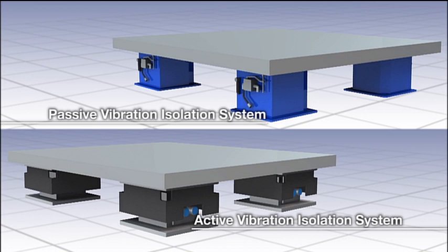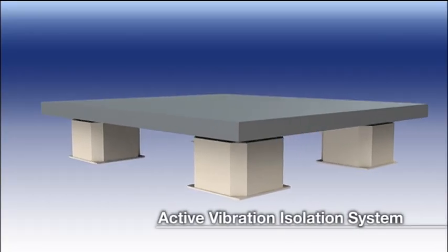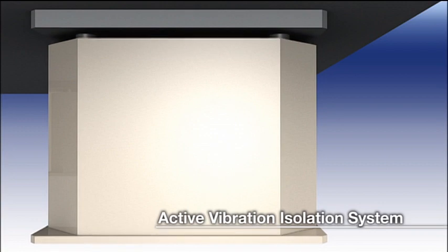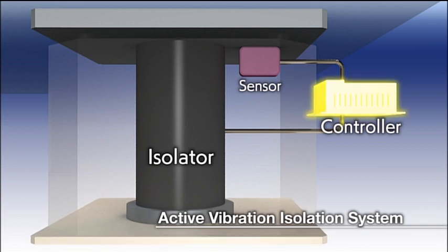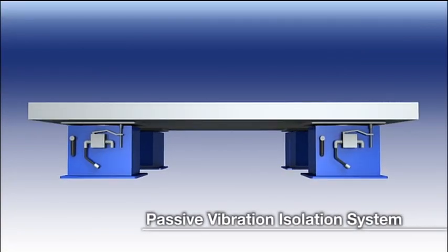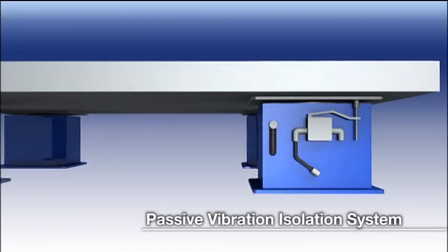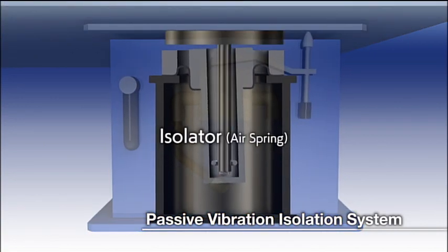Active and passive are the two types of precision vibration isolation systems. An active vibration isolator will neutralize or reduce vibration by sending opposite-phase vibrations against small vibrations caused by the installation environment or the floor itself. A passive vibration isolator uses air springs to reduce vibrations.